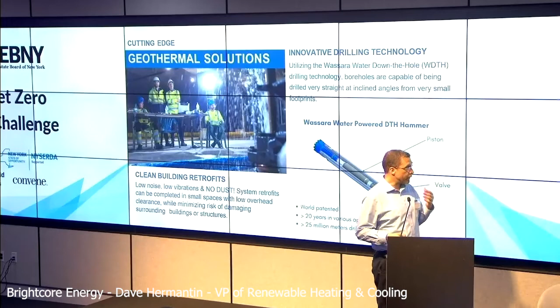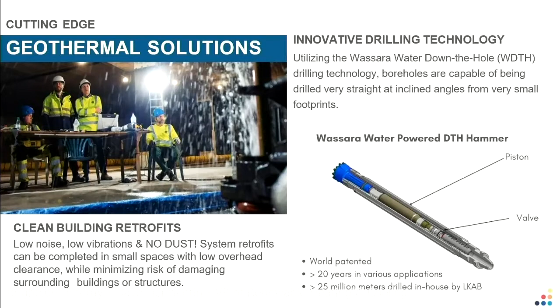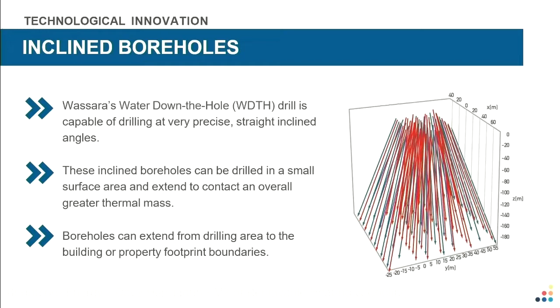This picture is from an installation that our partners did in Sweden that retrofitted a building with 80 boreholes in the basement of a building. And here's a computer graphic of that design. You may notice that this graphic is a bunch of lines, and they're angled as they extend downward. What this represents is the surface area inside of a building where this system was installed. It was about a 14,000 square foot open area in a basement parking garage, where they drill directly vertically and also at inclined angles. This allows us to capture a lot more thermal mass than could be considered before with conventional drilling technologies.